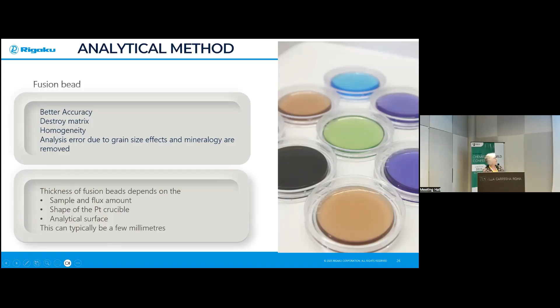The standards that we use need to have the correct concentration, otherwise we will not have an accurate and precise determination. So, as I mentioned, the fusion is the best for accuracy. We take away the error from particle size and matrix. We get a very homogeneous mixture, and we ensure that the thickness of the fused bead depends on the sample and flux amount, and the shape of the analytical mold will determine the analytical surface that we will measure. So here you can see an example of some fused beads, which are glass matrix. What about the calibration? So our software is very nice because we can create the 27 standards as fused beads.